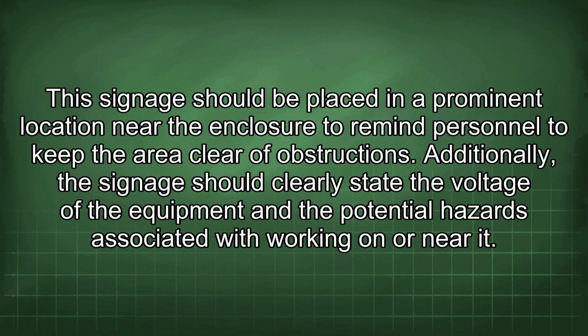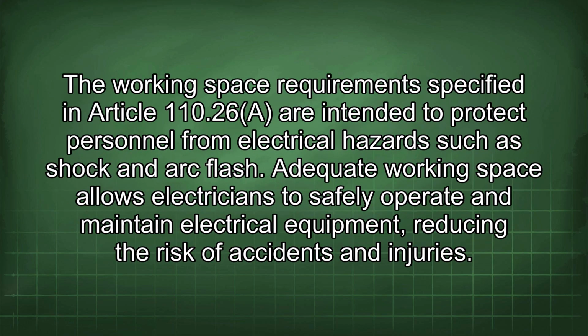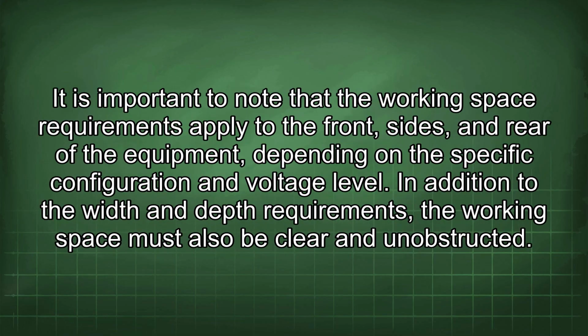on or near it. The working space requirements specified in Article 110.26 are intended to protect personnel from electrical hazards such as shock and arc flash. Adequate working space allows electricians to safely operate and maintain electrical equipment, reducing the risk of accidents and injuries. It is important to note that the working space requirements apply to the front, sides, and rear of the equipment depending on the specific configuration and voltage level.